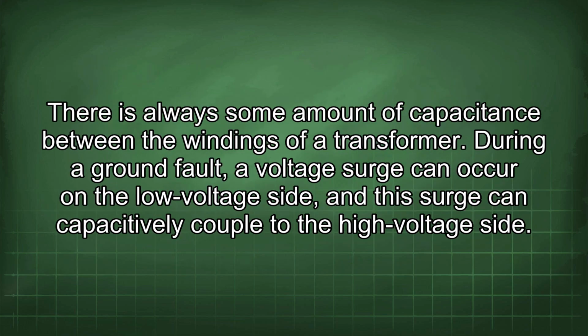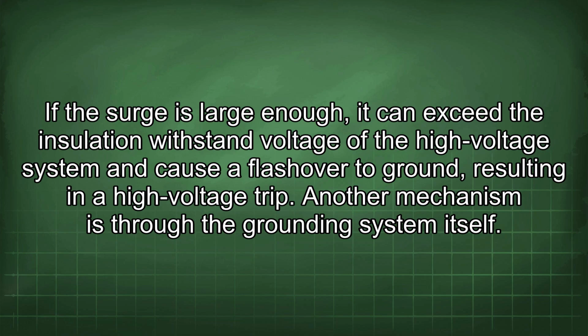There is always some amount of capacitance between the windings of a transformer. During a ground fault, a voltage surge can occur on the low voltage side, and this surge can capacitively couple to the high voltage side. If the surge is large enough, it can exceed the insulation withstand voltage of the high voltage system and cause a flashover to ground, resulting in a high voltage trip.